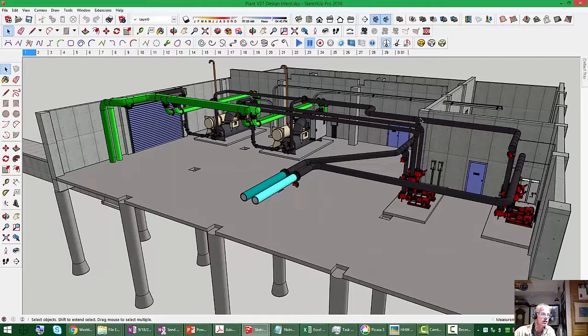That's basically the distinguishing characteristic of a variable flow primary secondary system. In other words, there's a pump dedicated to the chillers, or sometimes the pumps are in a header and the header is dedicated to the chillers, and then there's a totally separate set of pumps on a totally independent loop that distribute water to the loads. At this point it's a reasonable assumption that the big pipes leaving the plant are the pipes to the loads. So that information points you in the direction of this being a variable flow primary secondary plant.